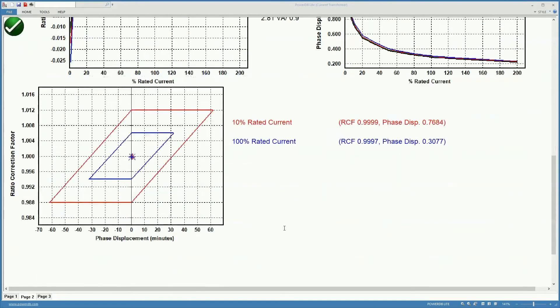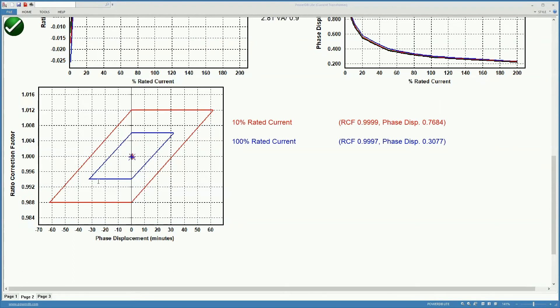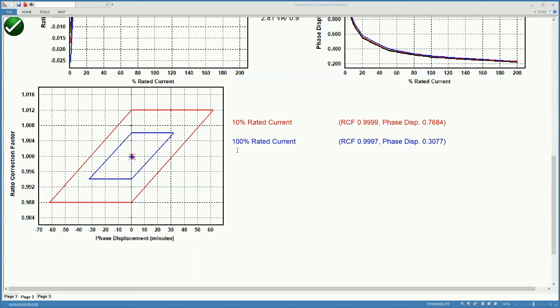And in this case we are showing the parallelogram, they call it the ANSI parallelogram, which shows where the CT is in phase displacement and minutes and ratio correction factor for a 10% of rated current. That would be the red parallelogram over here or at the 100% of rated current which would be the blue parallelogram over here.